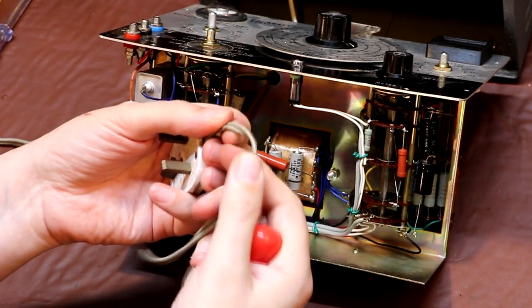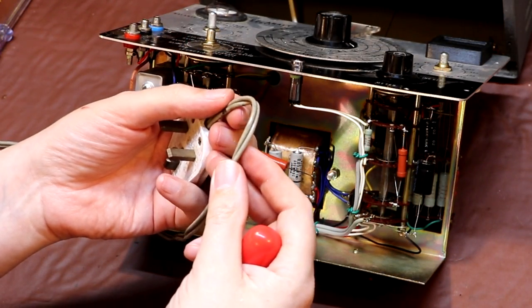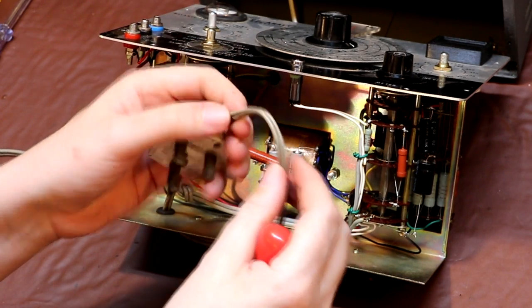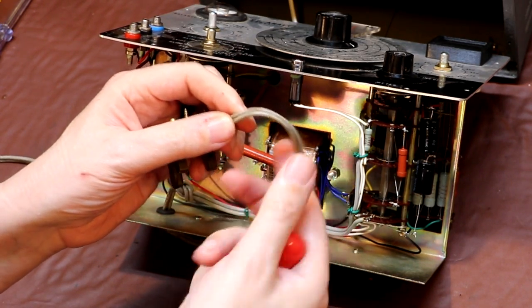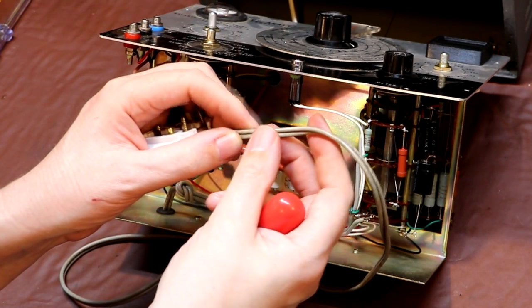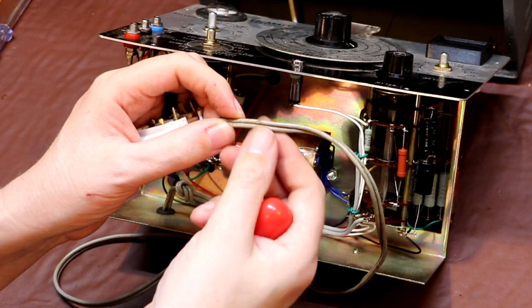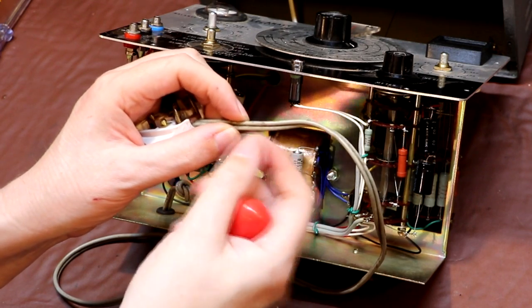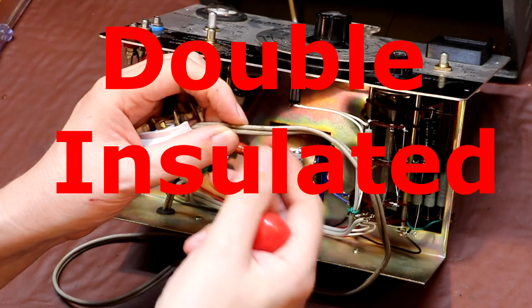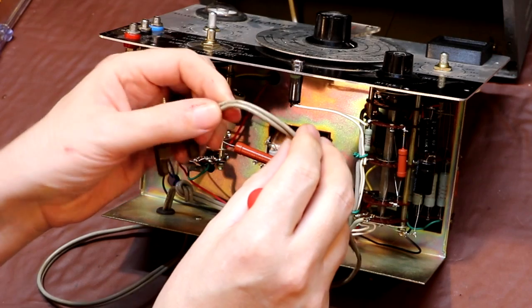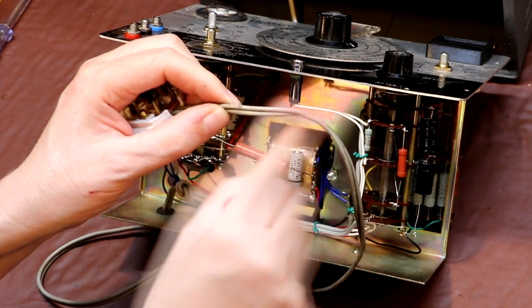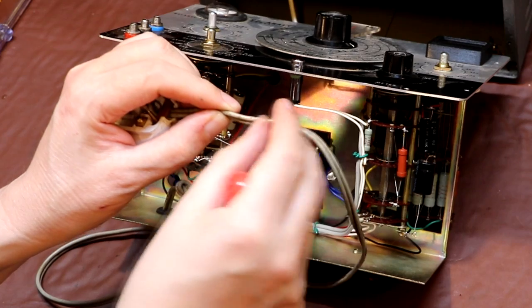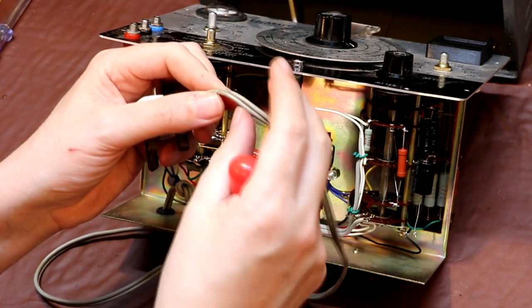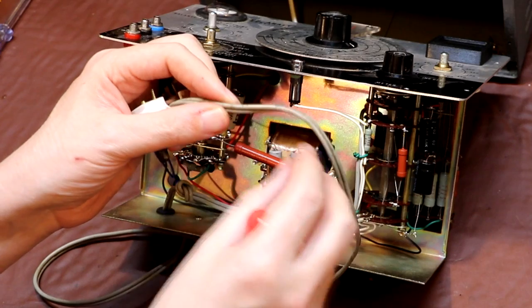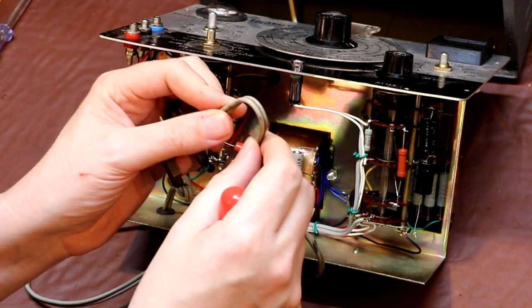Now of course the main reason for replacing this cable is because we want one that's three-core, but I also don't like this style of, again I'm going to call it American wire. To me this looks like bell wire in that it doesn't have any outer insulation. Of course the live and neutral wires are fully insulated, but I do prefer my cables to have an outer jacket on because it gives them that little bit more protection against any kind of abrasion. If you get any abrasion on this, you're directly going to start cutting in and exposing the inner conductors, whereas if you've got an outer sheath, well you've got a good chance of spotting this damage to the outer sheath before it actually cuts through.